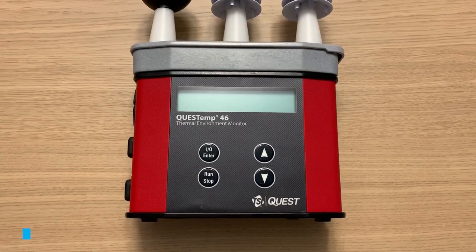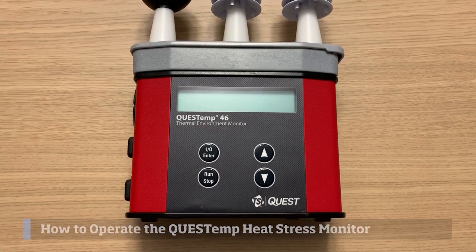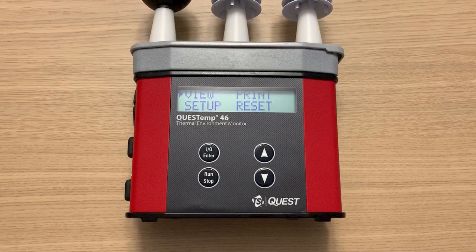In this video I'll show you how to navigate the setup menu of the QUESTemp heat stress monitor, as well as how to start and stop a run. First I'm going to turn on the instrument. You'll see a display of the battery voltage — it says 9.4 volts, plenty of battery. Note that the sensors need to be given 10 minutes to stabilize to the current environment after being placed in the work area.